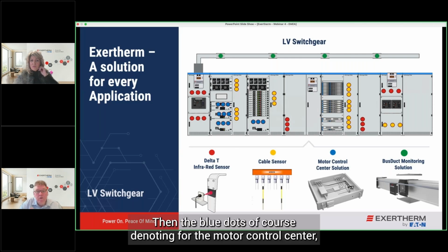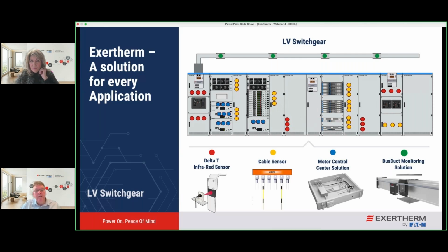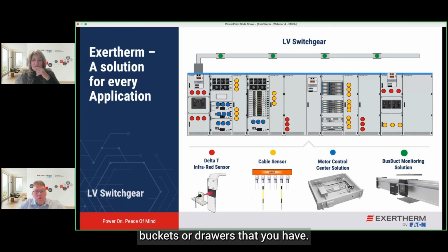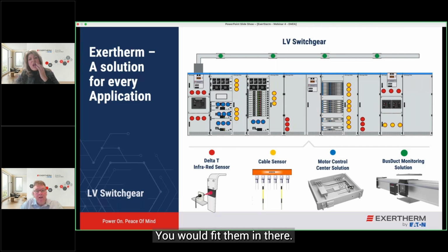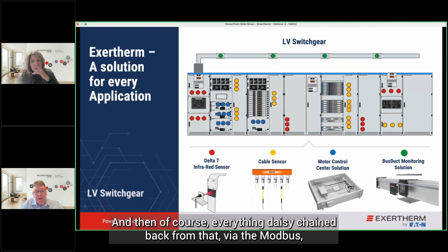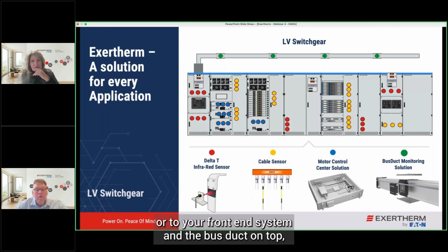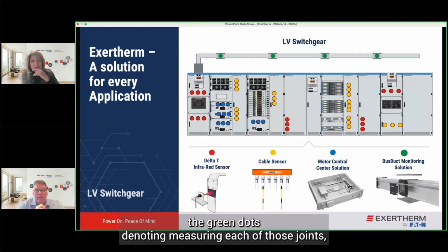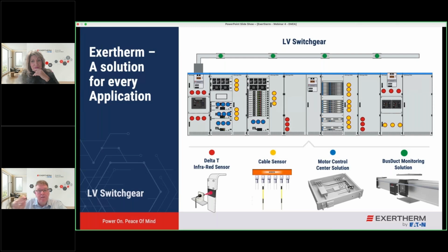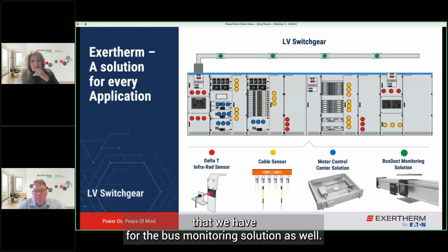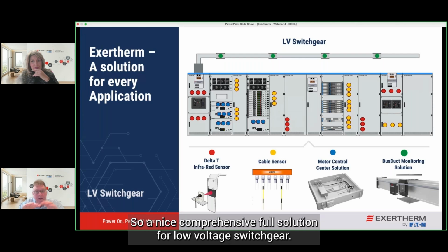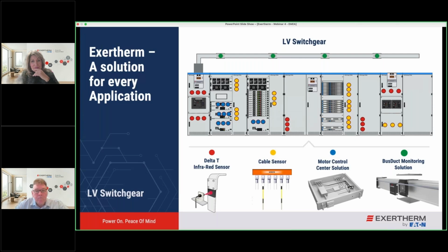Then the blue dots denote the motor control center buckets or drawers that you have, and you would fit them in there. Then, of course, everything is daisy chained back via Modbus RTU to your front-end system. And on the bus duct on top, the green dots denote measuring each of those joints for the bus monitoring solution as well. So a nice comprehensive full solution for low voltage switchgear.